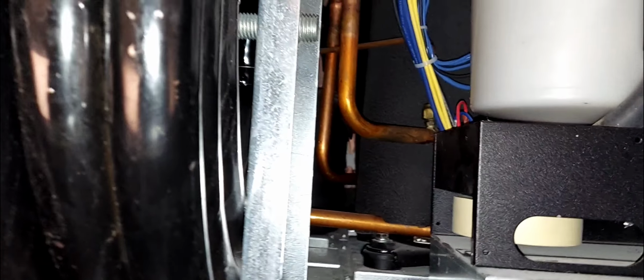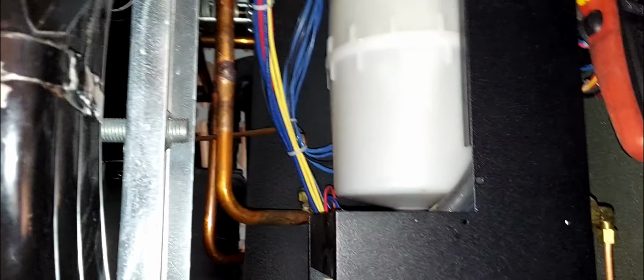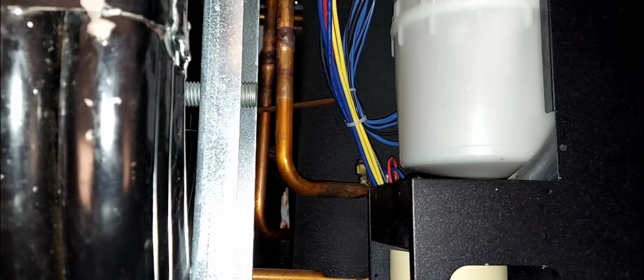So on this service call, I would say that it's an intermittent problem. I can't really do much with this because the humidifier does work, it does draw amps, it does boil. I don't know why that came up. We're going to have to monitor this unit further. All right, probably a second visit, it might reveal itself, but nothing I can do at this point. All right. Everything is working as verified here.